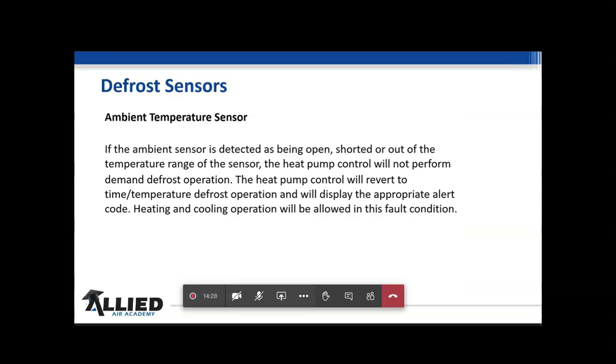So how do the sensors act when there's an issue or a problem? If the ambient sensor is detected as being open, shorted out, or out of the temperature range of the sensor, the heat pump control will not perform demand defrost operation. It will, however, revert to time and temperature defrost operation. So it'll still work, even though the ambient sensor's out.